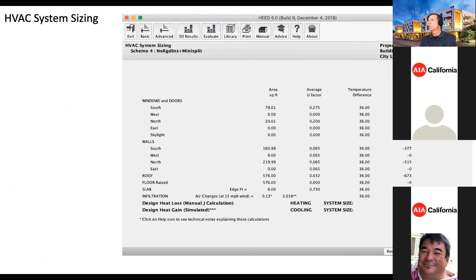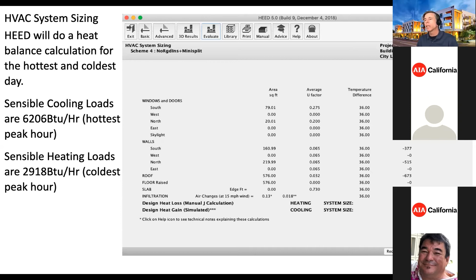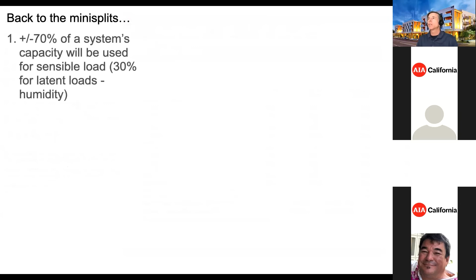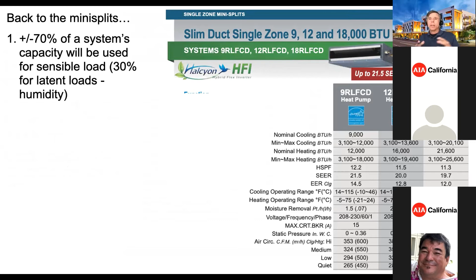And if I look at this, my HVAC sizing says for cooling, I need 6,206 BTUs per hour. And the sensible load for the coldest day, the heating load, is 2,918, not a whole lot of heating load. But now I'm back to the mini splits. A rule of thumb for this: when you look at your HVAC systems, it says the rated nominal cooling capacity is 9,000 BTUs, 12,000 BTUs, or 18,000 BTUs. The sensible capacity in that number is worth 70 to 75%.